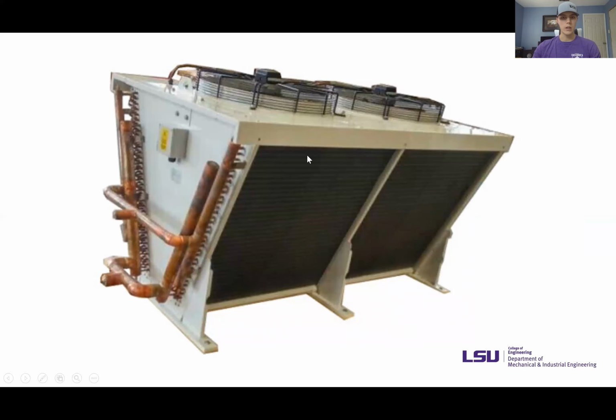So here's what a condenser would look like. The refrigerant would come in like this. They can either be 2 or 3 pass condensing coils. And what that means is the refrigerant will pass through the coils multiple times in order to remove more heat from the refrigerant. So as it makes several passes, more and more heat is taken out of it, and then finally it exits.